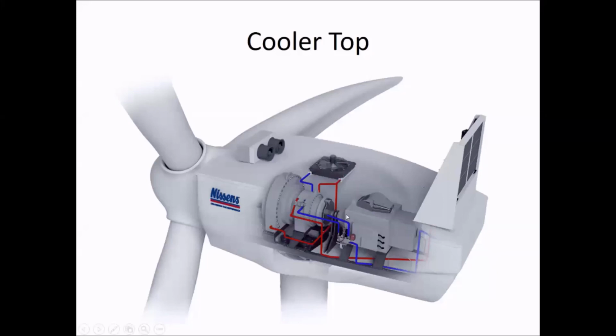So the heat generated by this will not be cooled. If the temperature of the nacelle reaches some particular limit, the nacelle automatically stops. Otherwise it will be a threat to the generator and gearbox, since these are very costly items and we cannot risk them. So there is a sensor actuated in the nacelle, such that when the temperature reaches some particular value, say around 30 to 32 degrees centigrade, or some say 38 to 40 degrees centigrade, the nacelle stops.